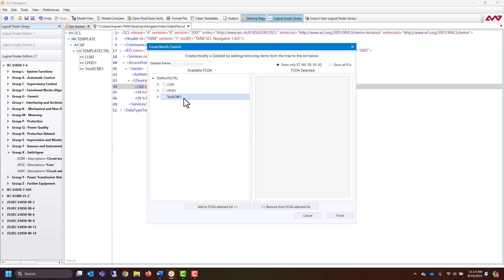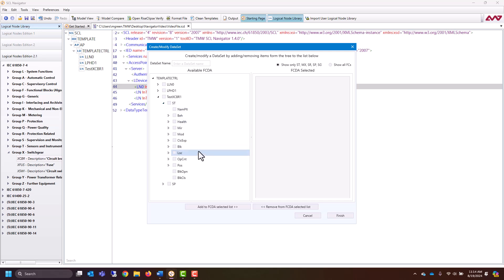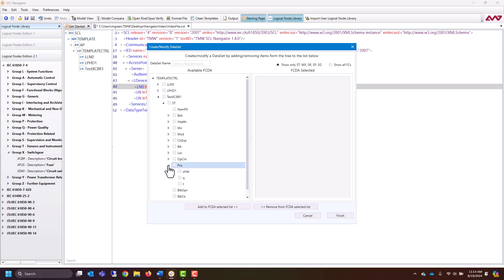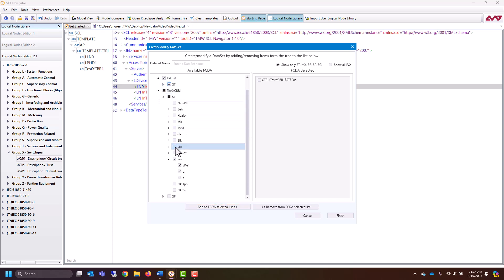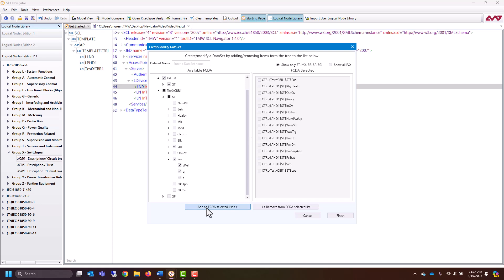From that dataset, we can now see our XCBR. If I open it up, you can look at things like the position of the XCBR, the health, or the behavior. So if I wanted to include the position inside of a dataset, I could just click this checkbox here and click Add. Of course, you can go into your other logical nodes and add other things as well. You'll want to give it a name and hit Finish.